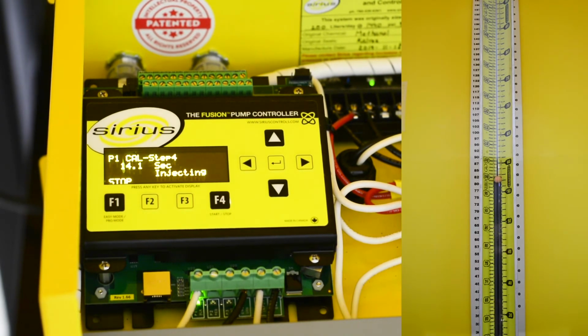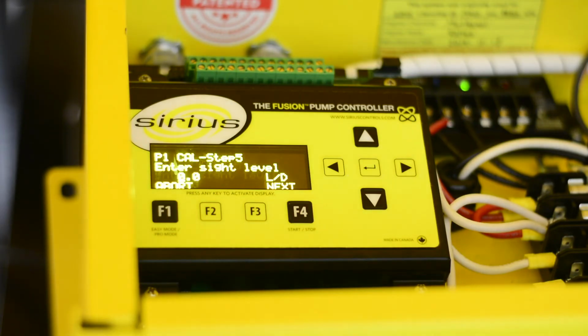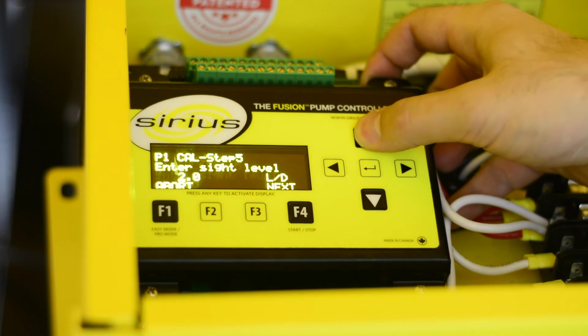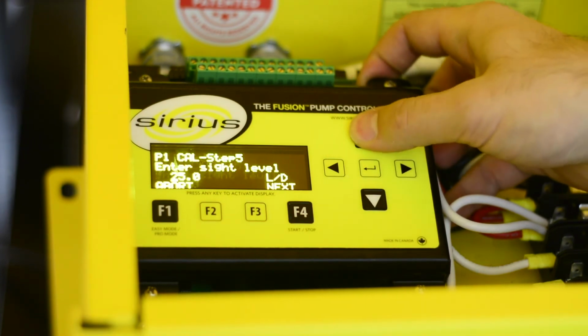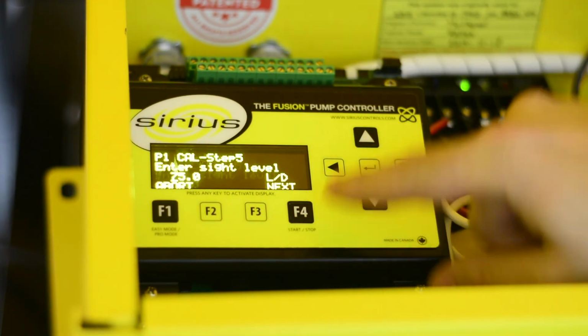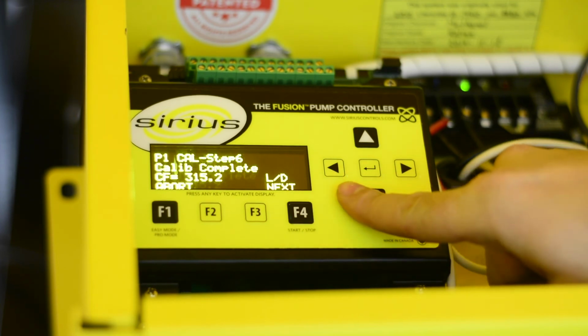This simple process eliminates the unnecessary time-consuming tasks required to adjust the rates of a conventional chemical pump. There are no charts, tables, or calculations required to determine plunger size, stroke length, or frequency and duration of duty cycle. The calibration is now complete, and the final sight glass reading is 25 liters per day, which we enter into the controller. Press F4 to continue, and the calibration is complete as indicated.